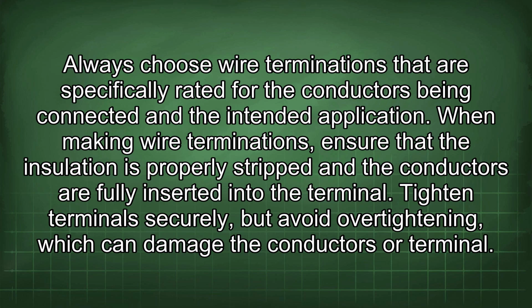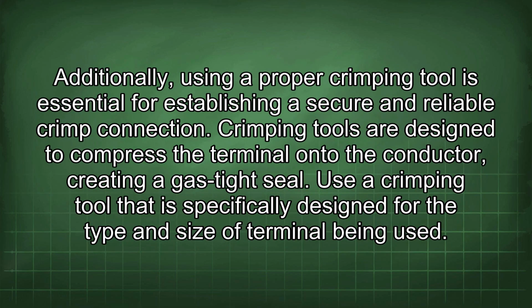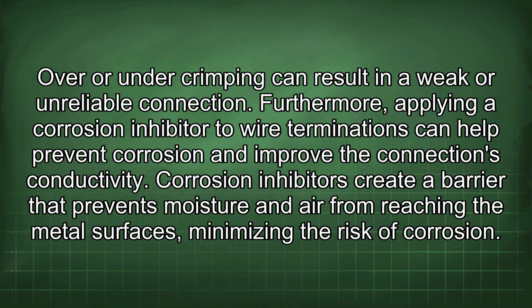When making wire terminations, ensure that the insulation is properly stripped and the conductors are fully inserted into the terminal. Tighten terminals securely, but avoid over-tightening, which can damage the conductors or terminal. Additionally, using a proper crimping tool is essential for establishing a secure and reliable crimp connection. Crimping tools are designed to compress the terminal onto the conductor, creating a gas-tight seal. Use a crimping tool that is specifically designed for the type and size of terminal being used. Over or under crimping can result in a weak or unreliable connection.